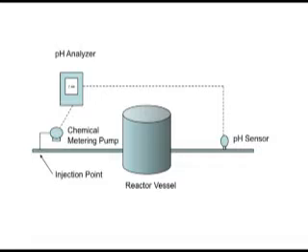A while back, I received an email from an automation practitioner who was having a great deal of trouble controlling his pH loop. He was interested in whether I thought that some kind of fuzzy logic or advanced control algorithm might work better than his standard PID controller. We emailed back and forth, and he finally sent me a drawing of his loop. pH was being measured downstream of a reactor vessel.